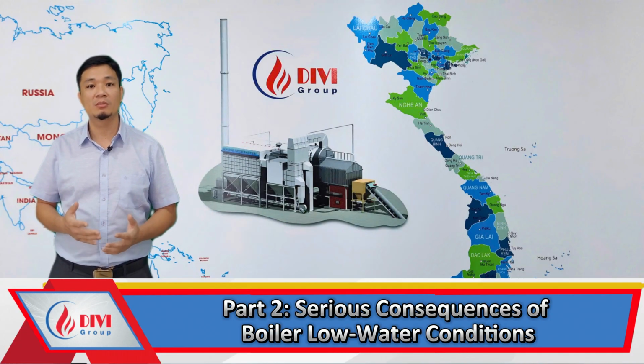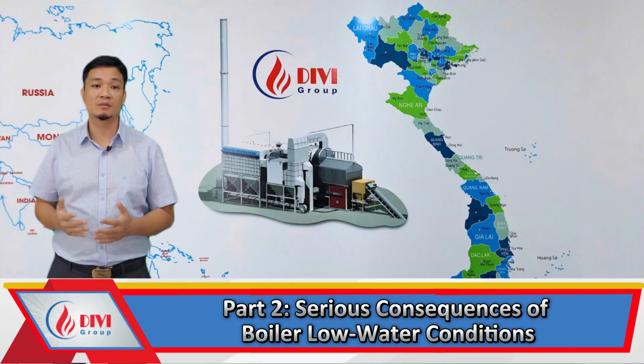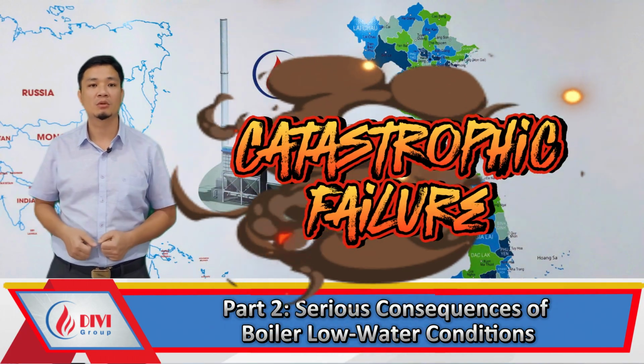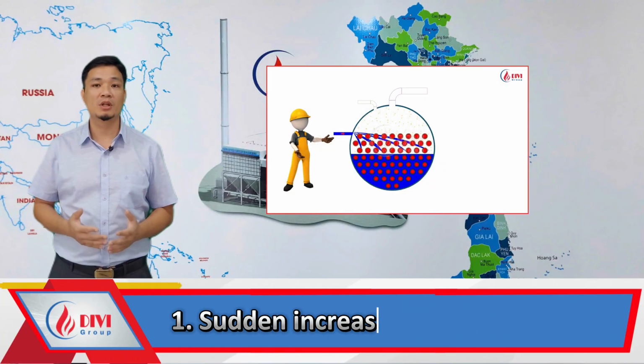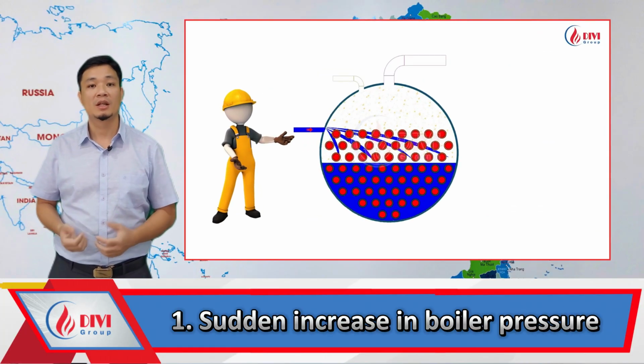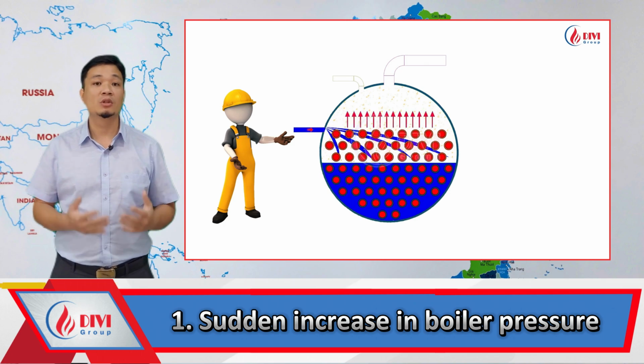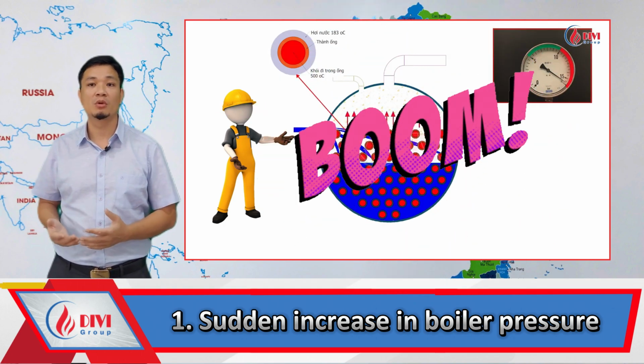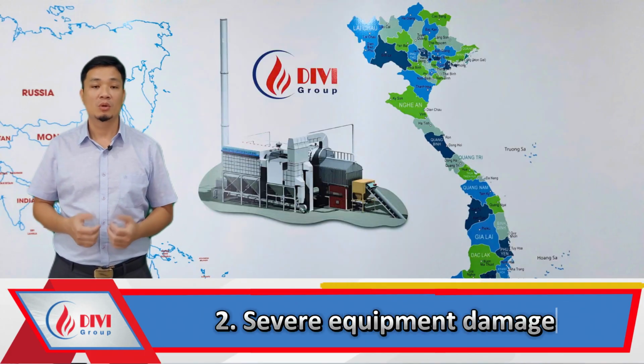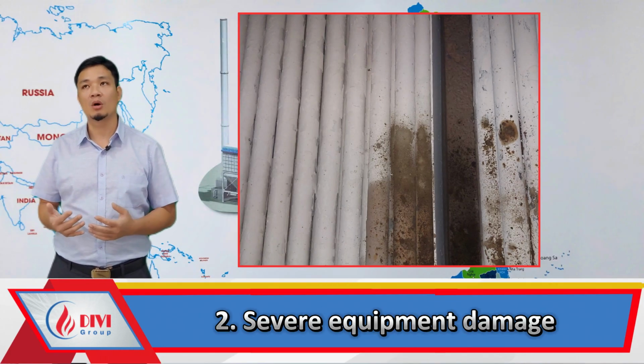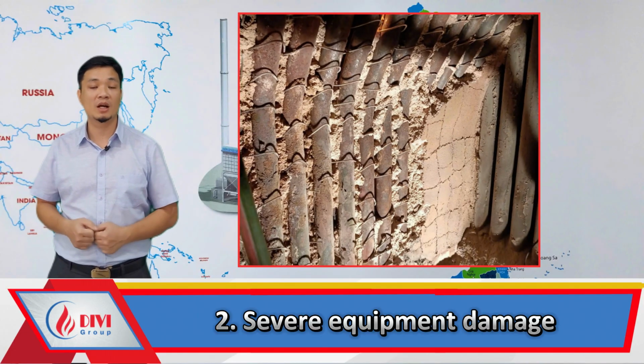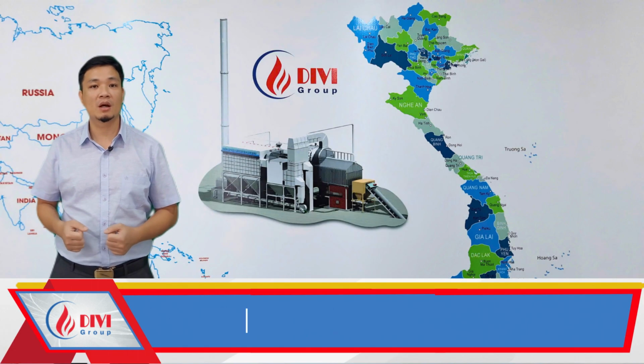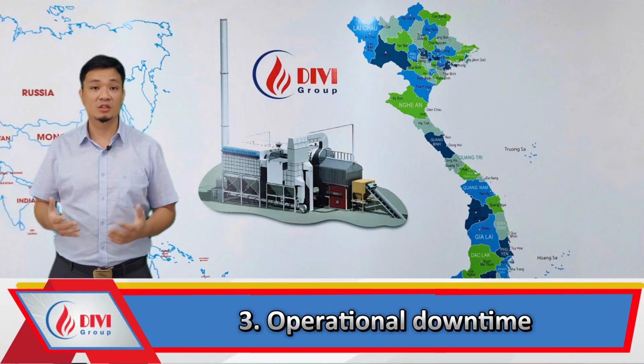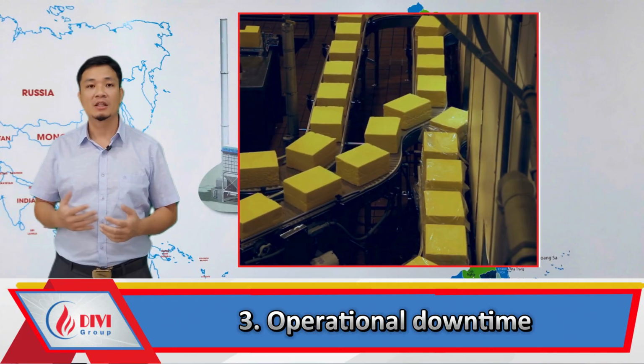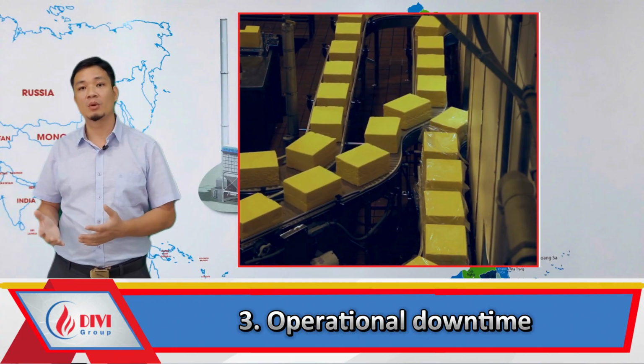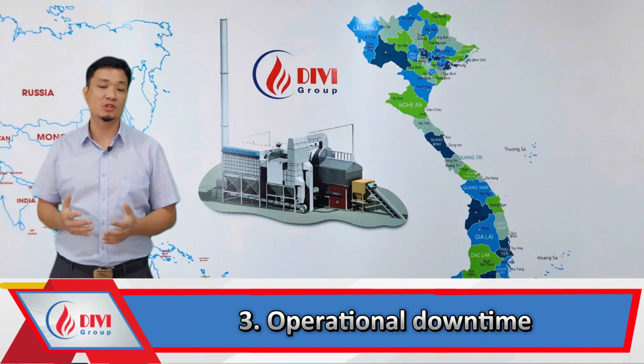Part 2, consequences of boiler dryout. Why it's so dangerous. Operating a boiler under dry conditions can result in catastrophic failures, sudden pressure escalation. Without water to absorb heat, metal surfaces overheat. Introducing cold water suddenly can trigger a boiler explosion due to thermal shock. Severe equipment damage: superheater tubes, water wall tubes, and furnace walls may warp, crack, or rupture due to overheating. Operational downtime: complete boiler shutdown may halt the entire production line, leading to significant economic losses. To avoid these consequences, let's proceed to the emergency response steps.